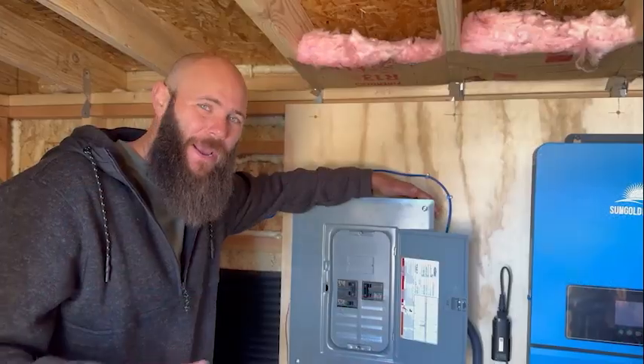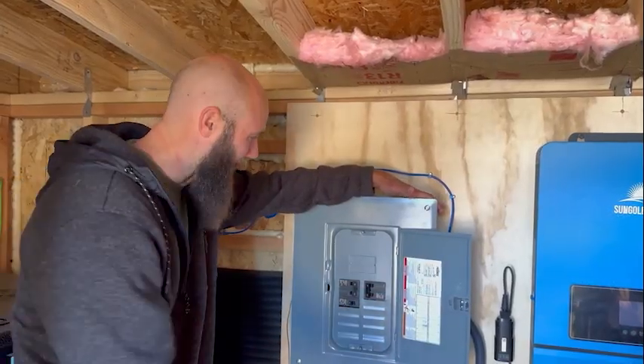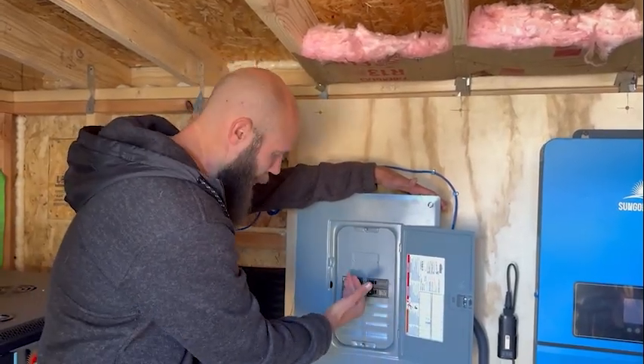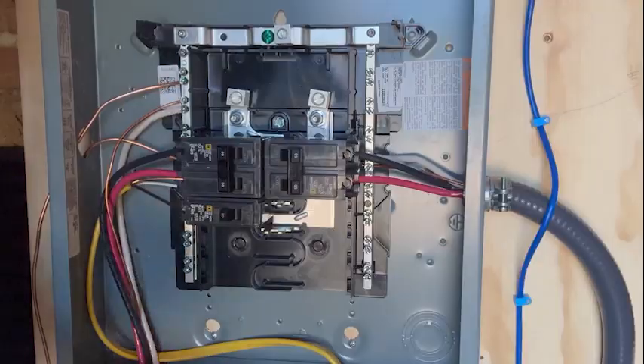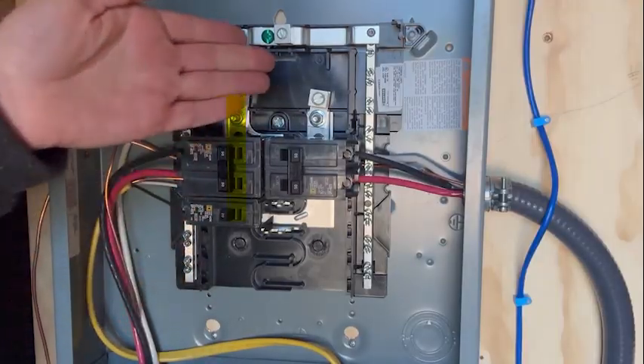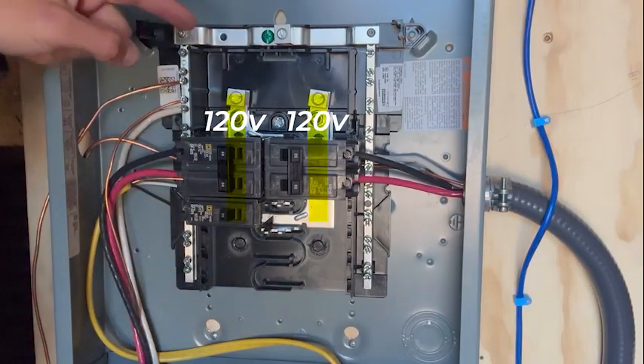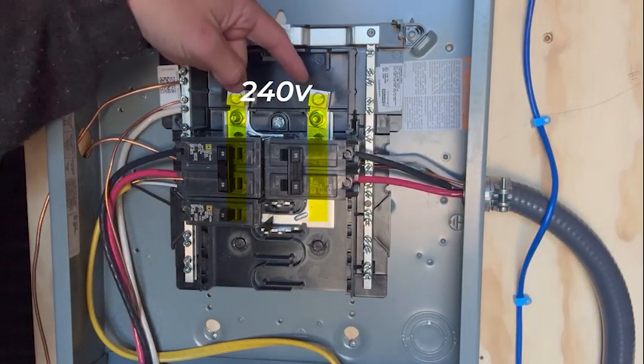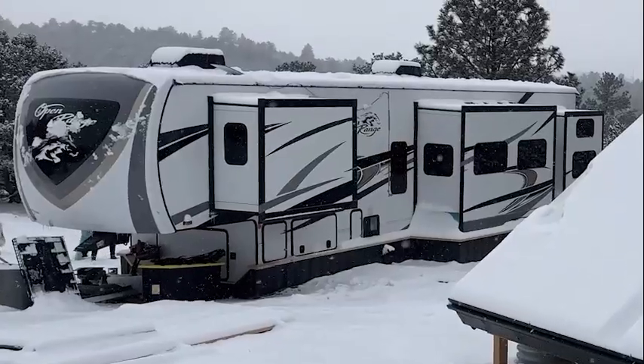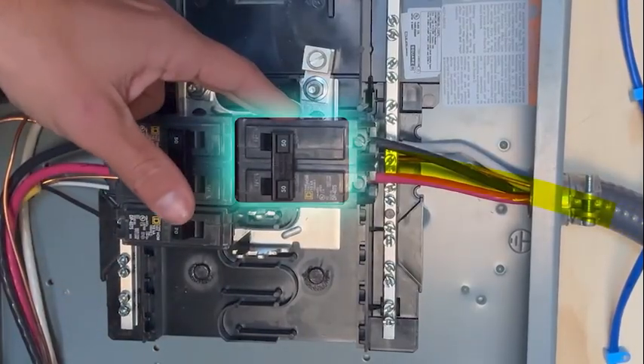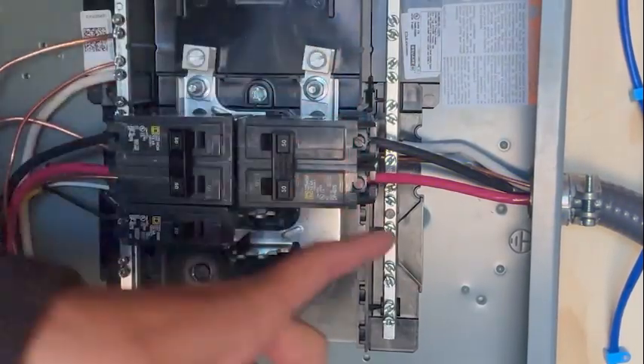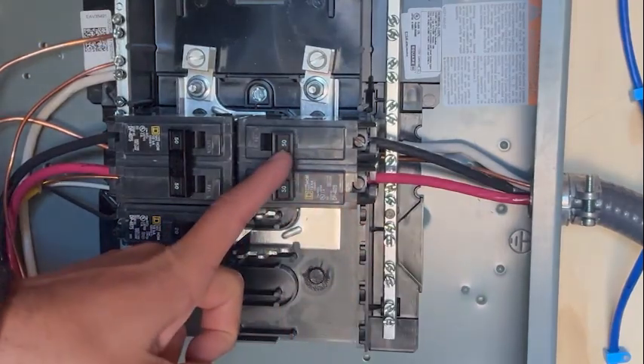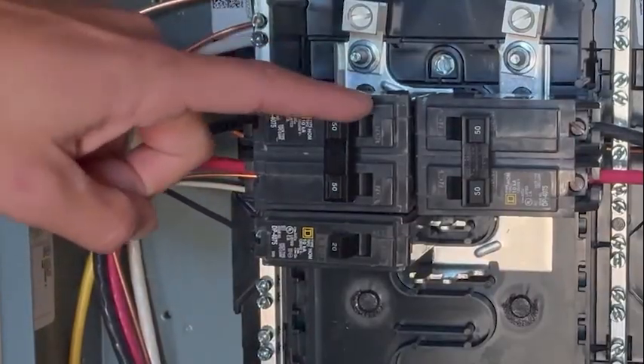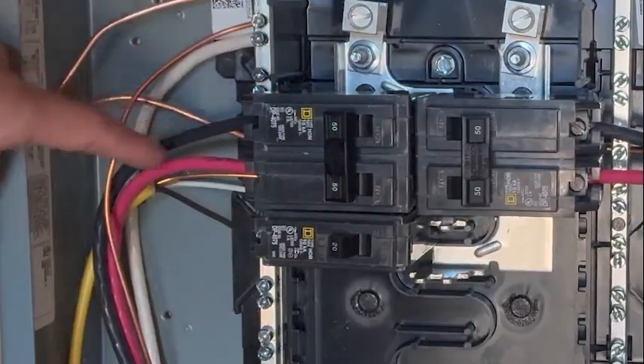Now, the circuit breaker panel is just a distribution box. Power is going to come into it and power is going to come out of it. Inside the panel are 2 bus bars, each carrying 120 volts. Together, they provide the split phase power needed for 240 volt loads. The inverter feeds both bus bars through a single 50 amp breaker, energizing the entire panel. Once the panel is live, individual circuits can pull power from it safely and independently.